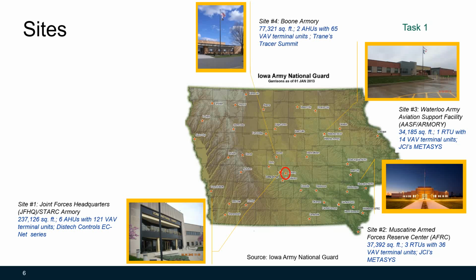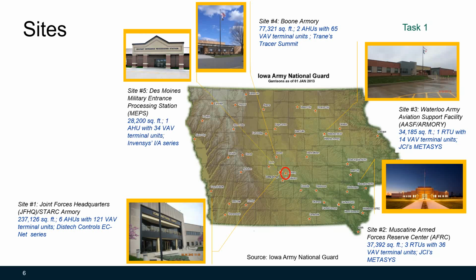Site number 4 is Boone Armory. This facility has 77,000 square feet, 2 air handling units with 65 VAV terminal units. This facility is controlled by Trane's Tracer Summit building automation system. And the last site is Des Moines Military Entrance Processing Station with 28,000 square feet, 1 air handling unit, and 34 VAV terminal units. The control system is Invensys IA series.